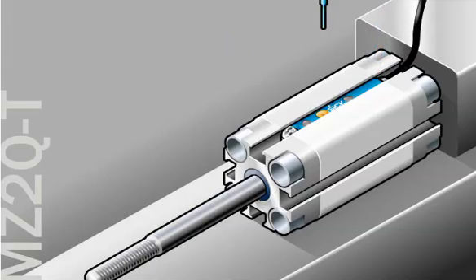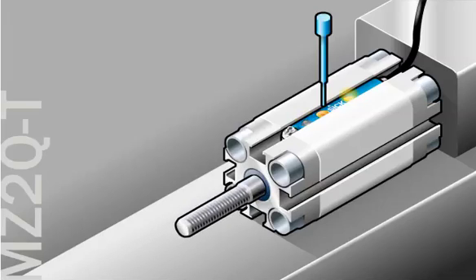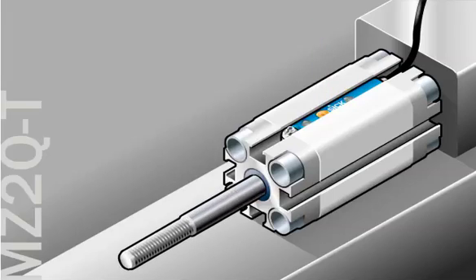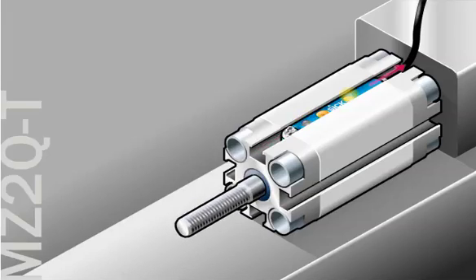To teach the sensor, move the piston to the first switching point location. Press and hold the teach button until the first LED blinks. Release the button. Move the piston to the second switching point location. Press the teach button one more time. Now, both locations are taught.